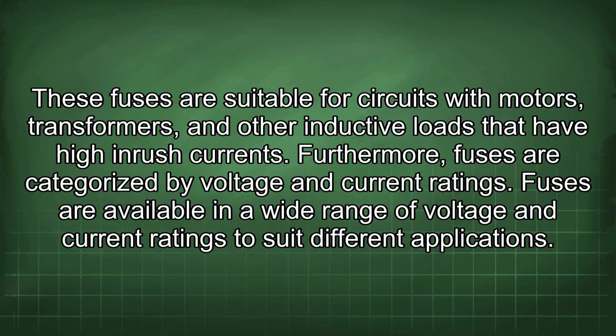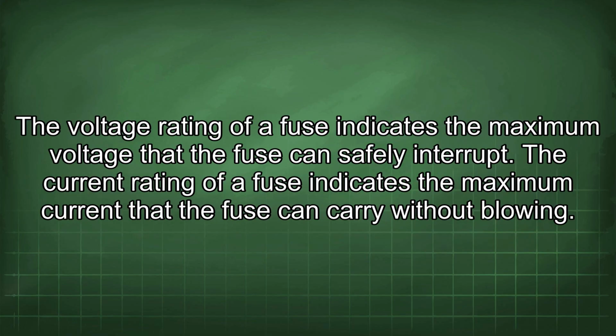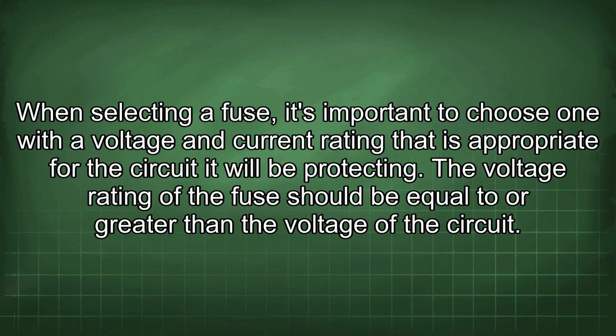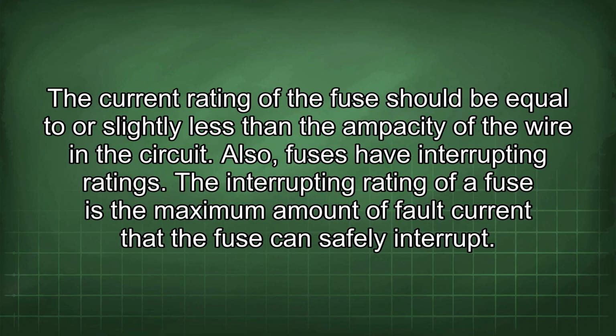Furthermore, fuses are categorized by voltage and current ratings. Fuses are available in a wide range of voltage and current ratings to suit different applications. The voltage rating of a fuse indicates the maximum voltage that the fuse can safely interrupt. The current rating of a fuse indicates the maximum current that the fuse can carry without blowing. When selecting a fuse, it's important to choose one with a voltage and current rating that is appropriate for the circuit it will be protecting. The voltage rating of the fuse should be equal to or greater than the voltage of the circuit. The current rating of the fuse should be equal to or slightly less than the ampacity of the wire in the circuit.